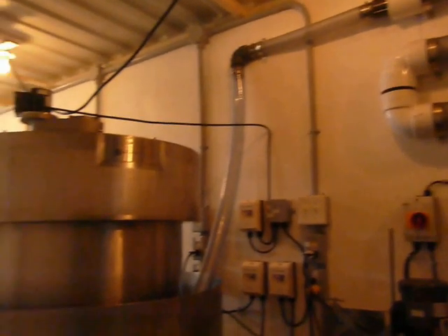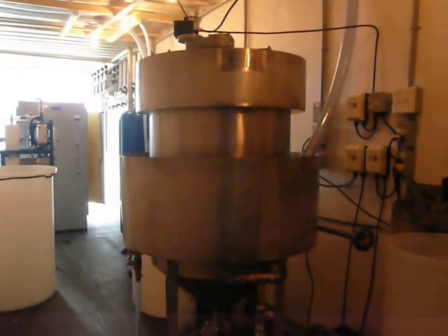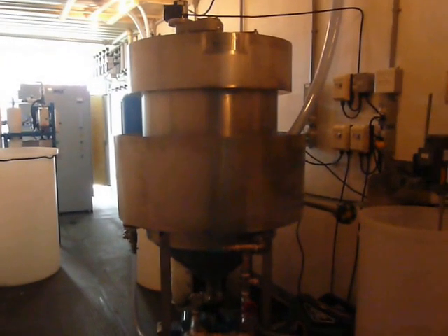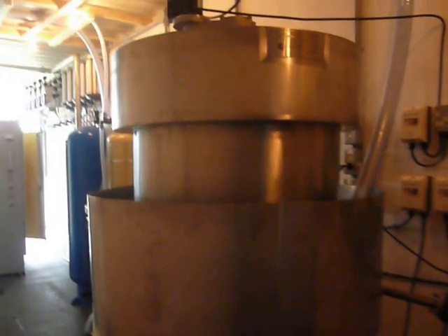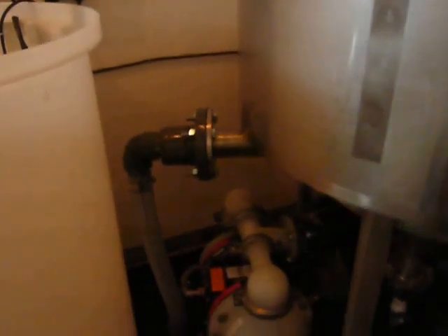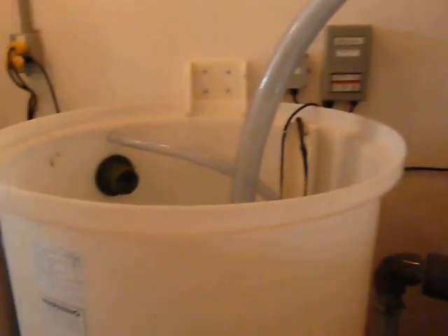And then this enters the dissolved air flotation clarifier. This clarifier allows then the flocculated, coagulated solids to be separated from the water. The solids are evacuated from the container using a sludge pump, where further dewatering can happen outside. And the clarified water enters this holding tank.